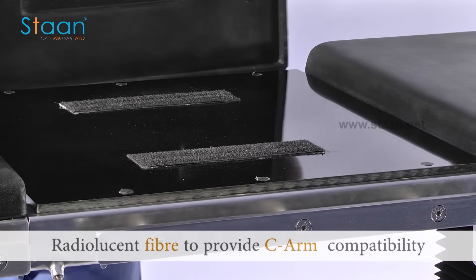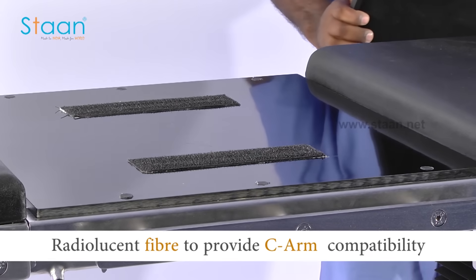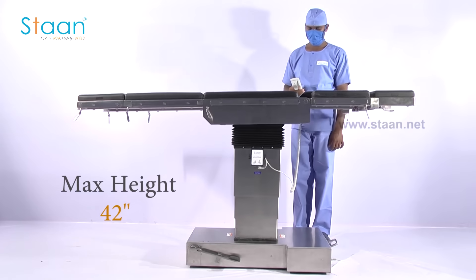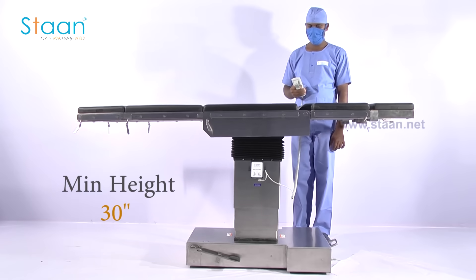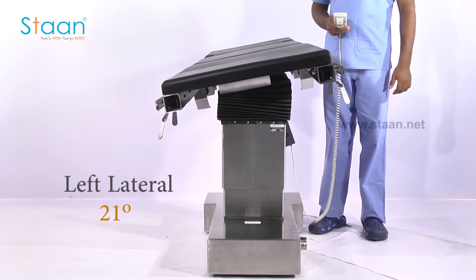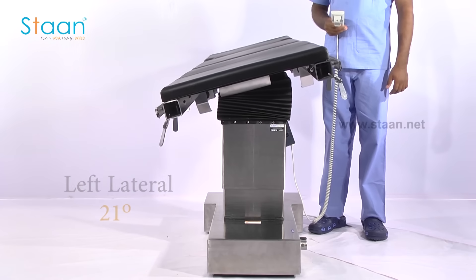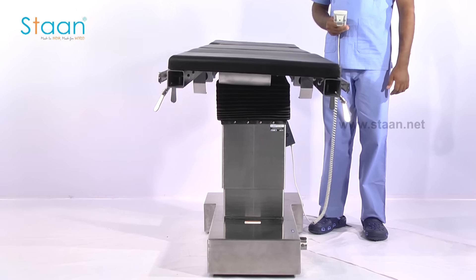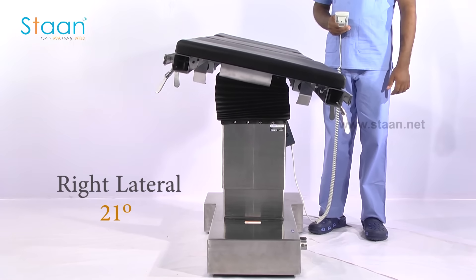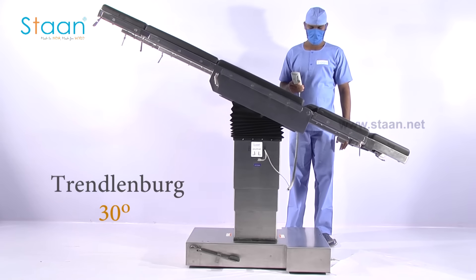The table top is covered with special radio-lucent strong fiber material in order to provide C-Arm compatibility. It can be operated to a maximum height of 42 inches and a minimum height of 30 inches, with left and right lateral tilt of 21 degrees, and Trendelenburg and reverse Trendelenburg of 30 degrees.